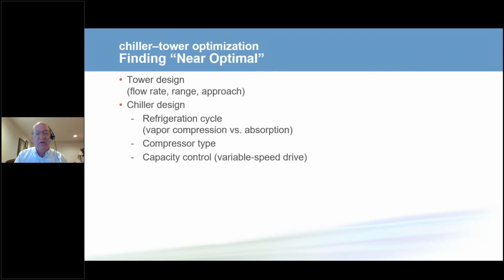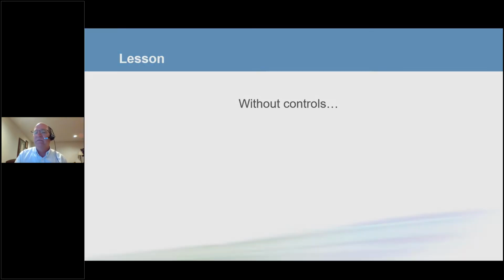Finding near optimal, we need to know what's the tower design. What type of chiller do we have? That line I showed on the graph, that changes. Is it a centrifugal? Is it a scroll chiller? Does it have a variable speed drive? So that changes. But then the two variables are, all we need to know is what is the chiller load and what's the outside air wet bulb temperature, and that optimal temperature can be calculated. So our lesson here is without controls, it isn't a system.